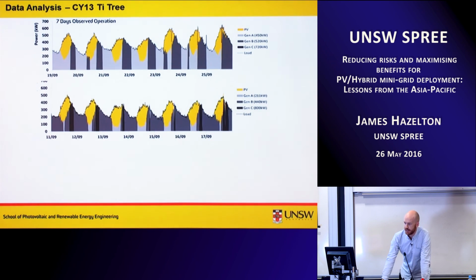This is what 7 days of operation looks like at both sites. You can see that Power and Water operate their diesels in a non-simultaneous manner. They size their generators first of all so that there are a few different sizes available, and they pick the one that they want to run at that particular time. So across 7 days you see this profile where the yellow is contributing to the load, which is the dotted line, reducing the peak load during the daytimes, and the diesel generators will be scheduled according to what the remaining load is in these systems.